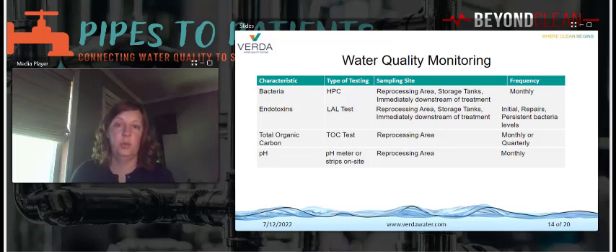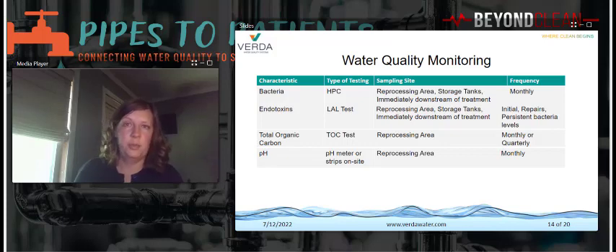Typically, facilities test for bacteria at one location, immediately after the reverse osmosis or the DI tank. While this is important, for sampling location, TIR 34 recommends also testing at the critical water point of use, immediately after the last water treatment step, on the return of the critical water recirculation loop, and in the storage tank if one is used. By testing comprehensively, not only will you have confidence there's no bacteria growth in your water system, but if bacteria is detected, you'll have more data to troubleshoot and pinpoint where in the system the contamination is likely occurring.